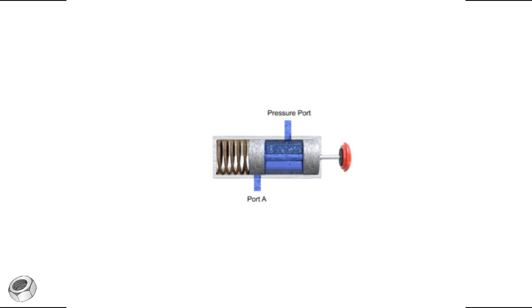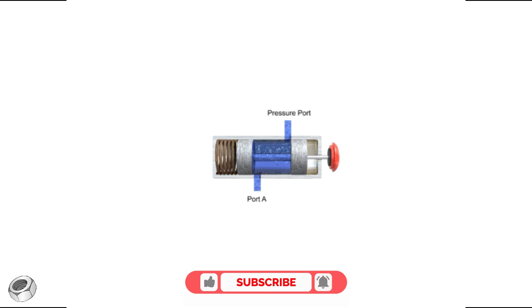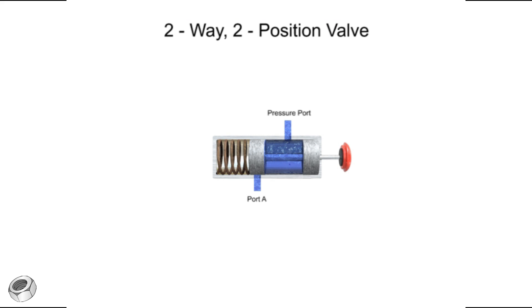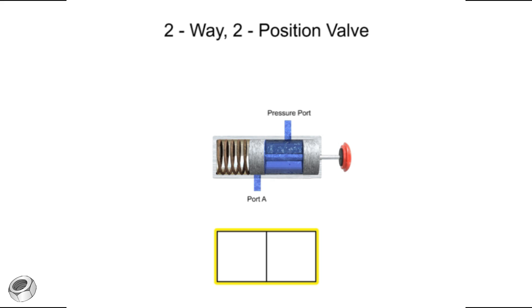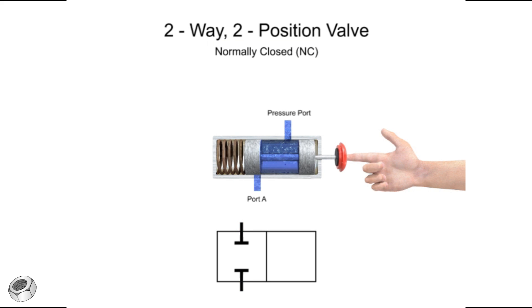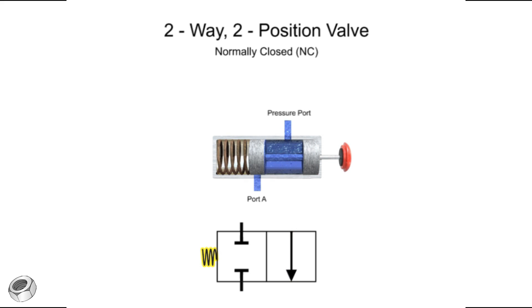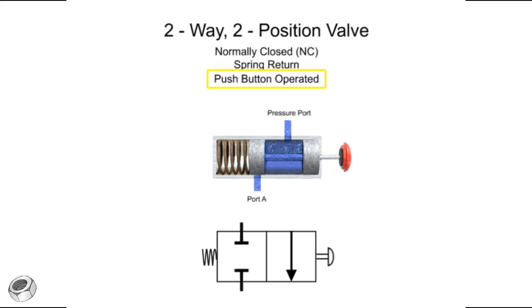Here is a similar valve to the one previously shown. It has two ports and two positions, so it is also a two-way, two-position valve. In the normal non-actuated position, both ports are blocked — therefore, it is a normally closed valve. When the valve is actuated, fluid is allowed to flow from the pressure port to port A. A spring returns the valve to its normally closed position, and a push button actuates it to the open position. Therefore, this valve is a two-way, two-position, normally closed, spring return, push button operated valve.